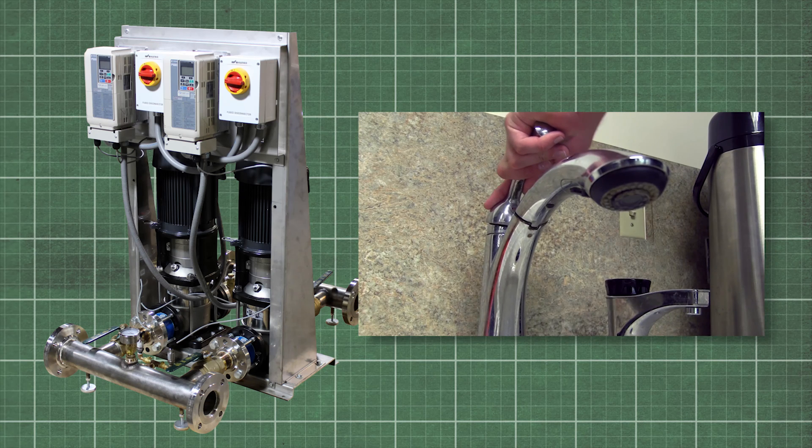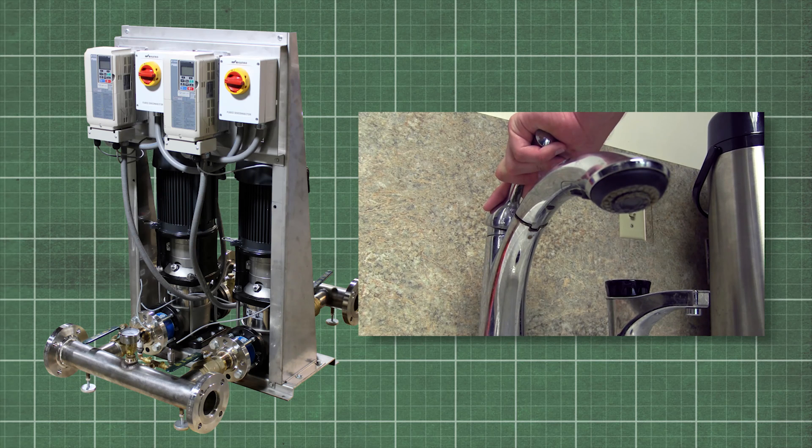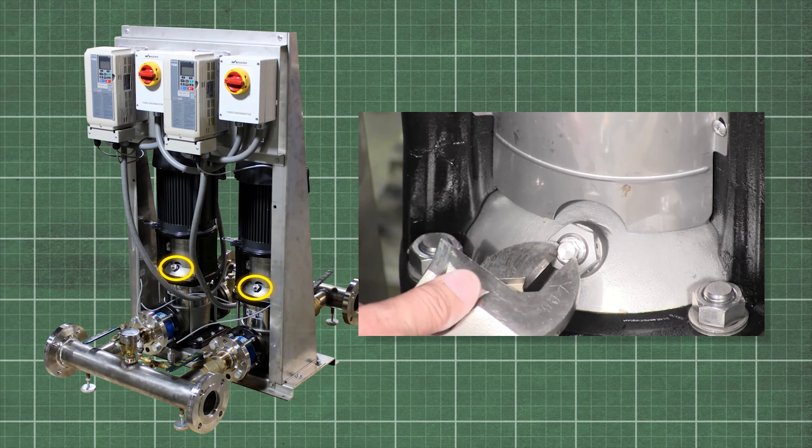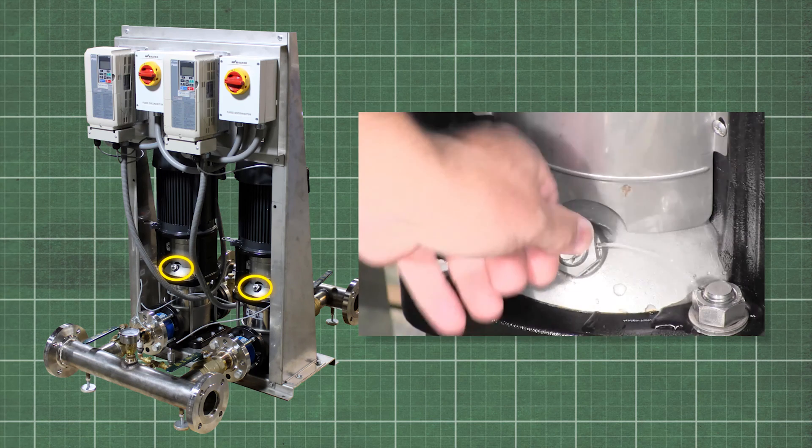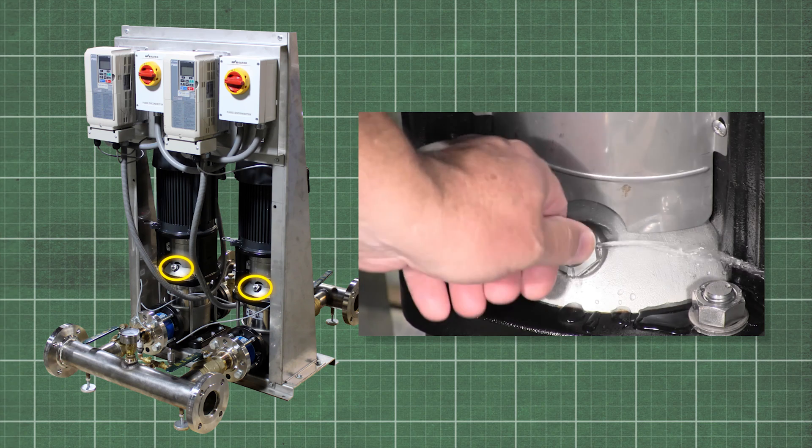If there is some incoming pressure, open a faucet after the pump. This will force all the air out of the pump and fill it with water. Check to make sure the pump is still fully primed by opening the prime valve on the discharge side of the pump. When fully primed, you will see water streaming out like this.